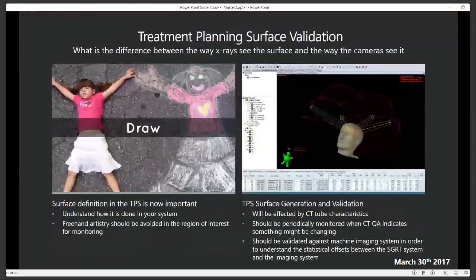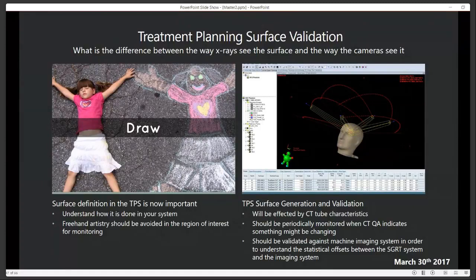And finally, what we're going to talk about is treatment planning system validation and QA. If you look at the little girl here on the left, if I was to draw her in chalk on the right and try to fuse those two surfaces together, I would not get the accuracy I was hoping for. You need to understand how your treatment planning system, in the same way, is generating the DICOM surface you're setting up to, and what the statistical discrepancies are between the way an X-ray sees the surface and the way your surface-guided radiation therapy system sees the surface. The statistical difference, if you choose the right thresholds, should be very, very small.